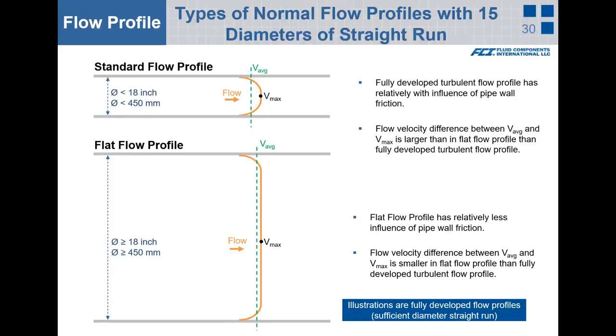In an 18-inch or smaller diameter pipe, you have a standard turbulent flow profile where wall friction drags velocity down, making maximum velocity at the pipe centerline. In 18-inch and larger pipe or duct diameters, friction plays less of a role and the profile is flatter. Therefore the meter needs to be calibrated differently — to a flat flow profile, like a wind tunnel type calibration, for 18-inch and larger.